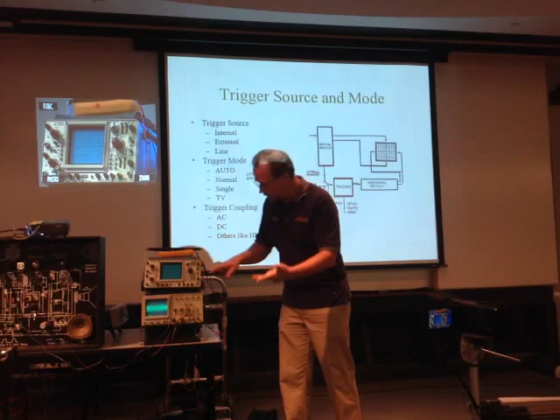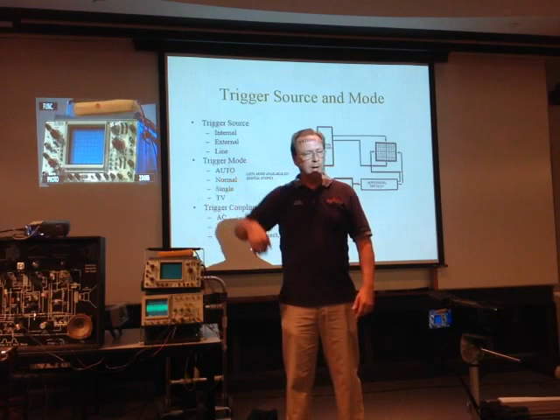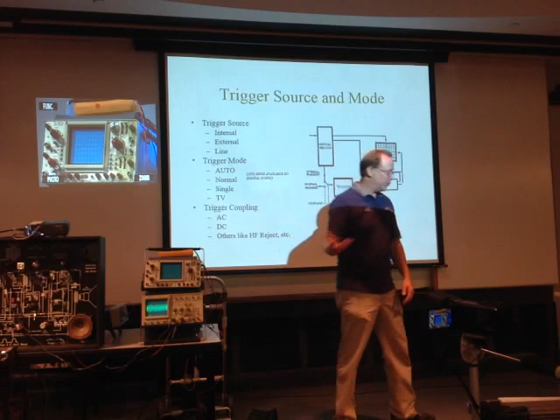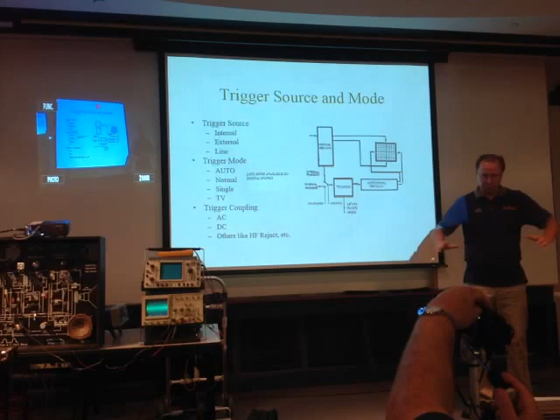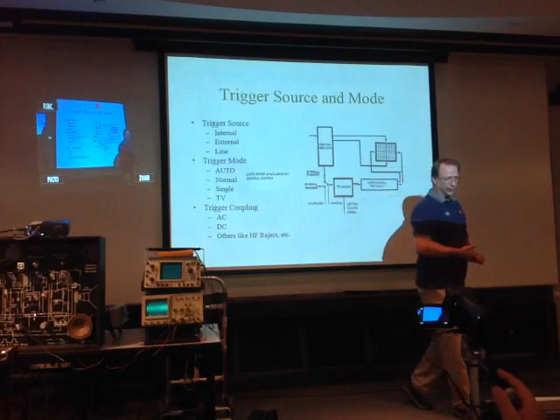But what do you notice about this? One of the most common ones I told you to use: auto, AC coupling, and internal trigger. All those are at the top of the controls. Take all the trigger controls, bring them to the top. Most old Tektronix scopes are like that, and a lot of other manufacturers copied that convention. Just bring all the trigger controls to the top, and you're set up to auto trigger, AC couple, internal. And you're good to go.